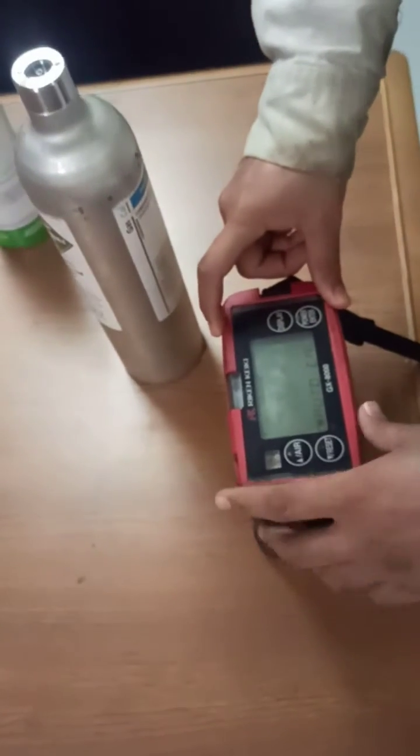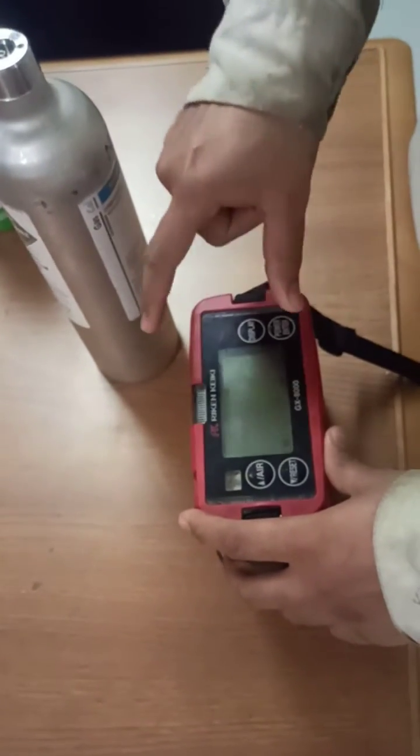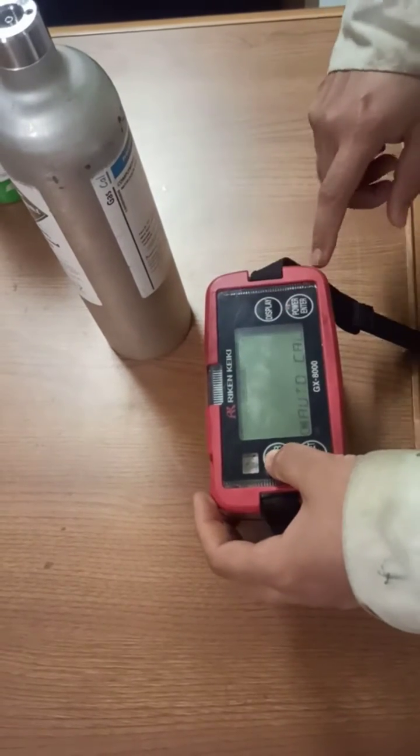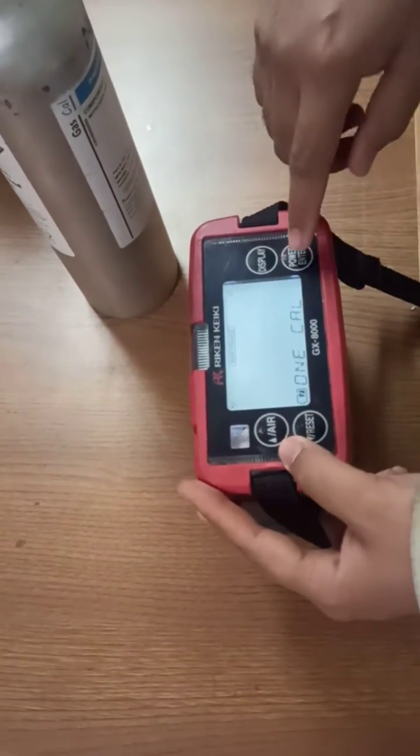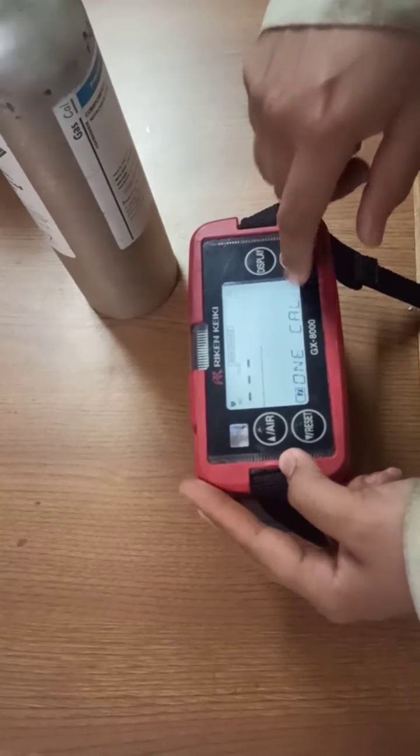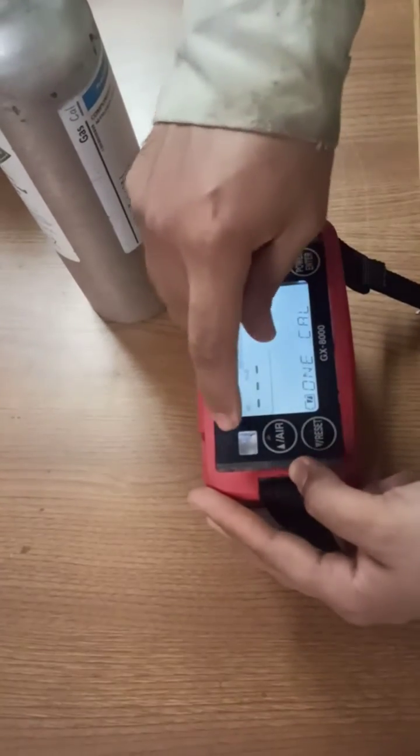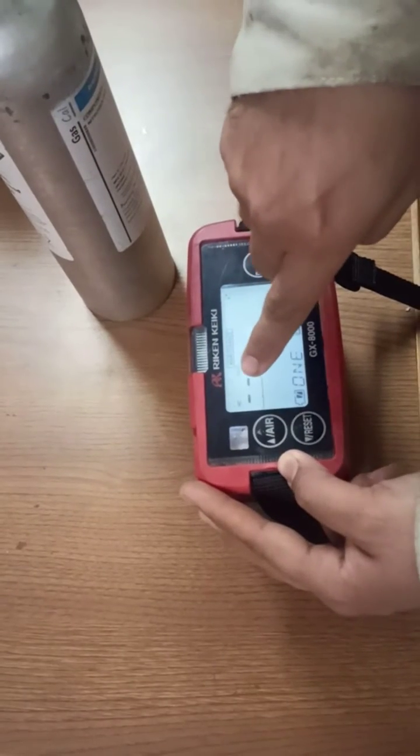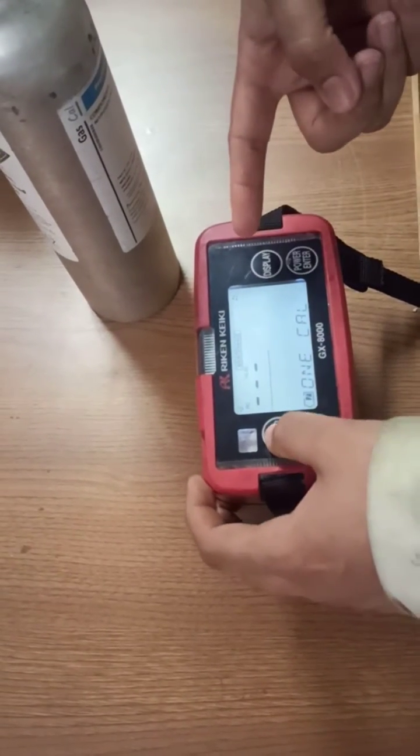Now we will perform one cal. That was auto calibration. Now we will perform one cal, so we will choose the option of one cal and press enter. In one cal, you can only do the calibration of one sensor at a time, so we will choose O2 sensor.